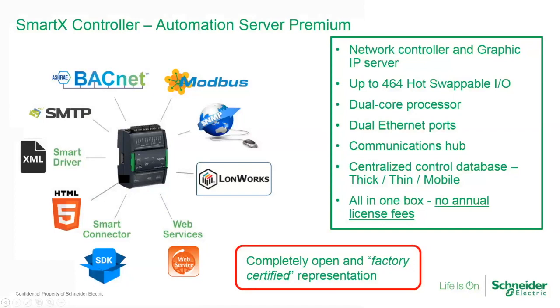There are some really important things to note about this ASP. Two in particular: one is it has dual Ethernet ports. All network controllers already have one Ethernet port—that's how they've always sat on that top line I mentioned previously. That second Ethernet port opens us up to run Cat5 cable to all of our field controllers in the facility. This gives us that robust infrastructure to build off moving forward, so when your owner comes to you in 9 years and says a new thing's been invented and they'd like to pull data from the system, you already have that platform in place.